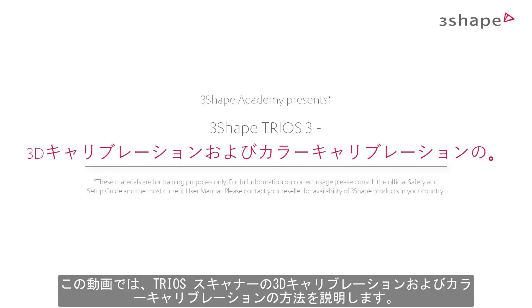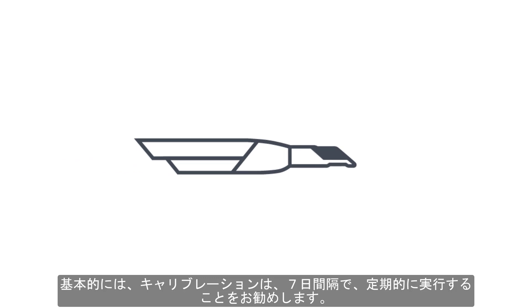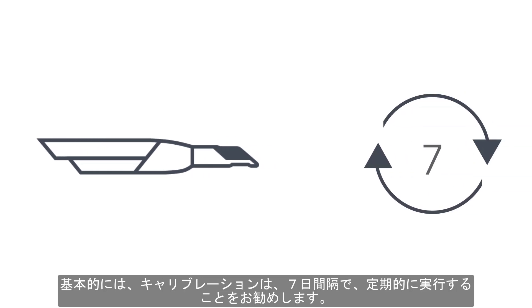In this video, we will go through steps of 3D and color calibration of the TRIOS scanner. By default, it is recommended to calibrate every 7 days.